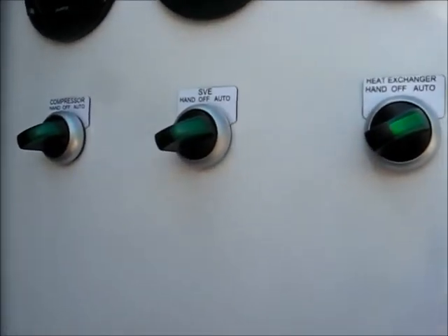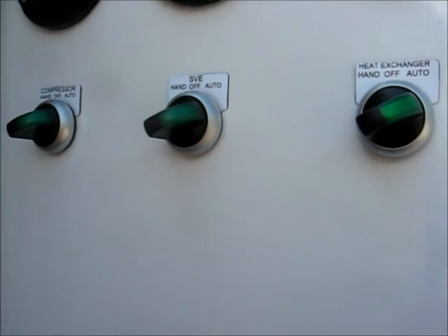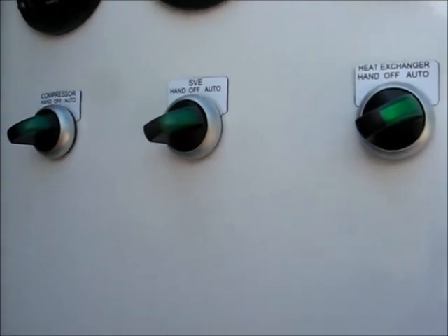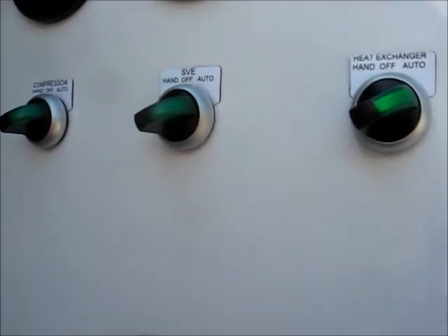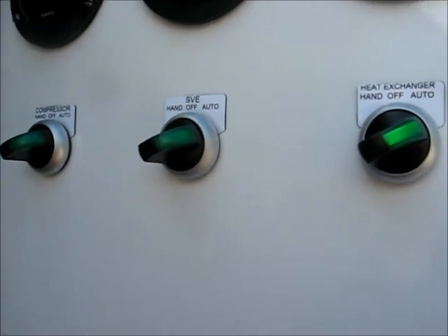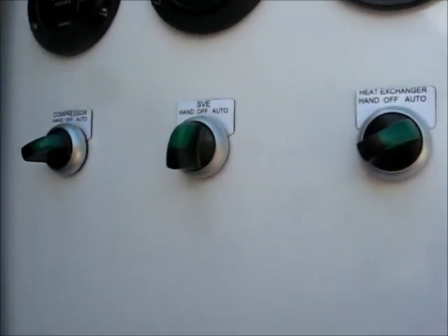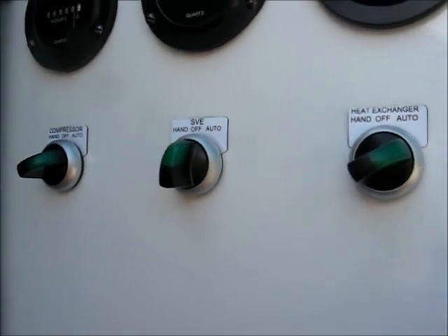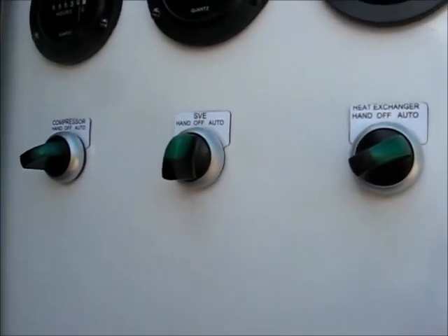The time delay must have been defeated from the SVE, but you can hear the air compressor came back on when we turned the heat exchanger on. Now if I turn this SVE off, it should drop everything out. You can hear everything shutting down, all the lights off. So the last thing I want to show you is that time delay.